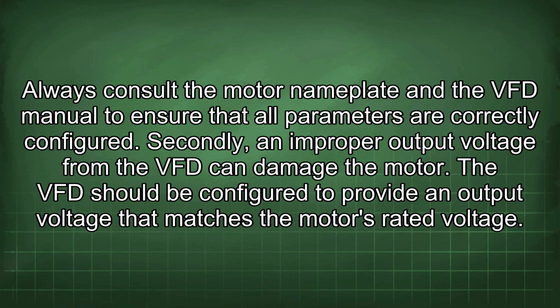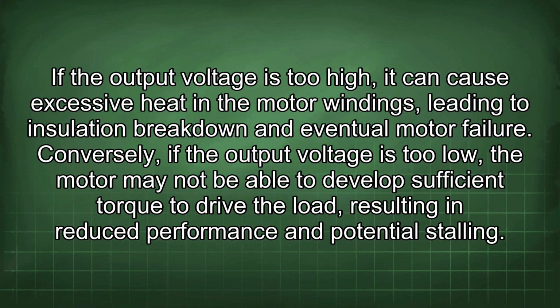Secondly, an improper output voltage from the VFD can damage the motor. The VFD should be configured to provide an output voltage that matches the motor's rated voltage. If the output voltage is too high, it can cause excessive heat in the motor windings, leading to insulation breakdown and eventual motor failure. Conversely, if the output voltage is too low, the motor may not be able to develop sufficient torque to drive the load, resulting in reduced performance and potential stalling.